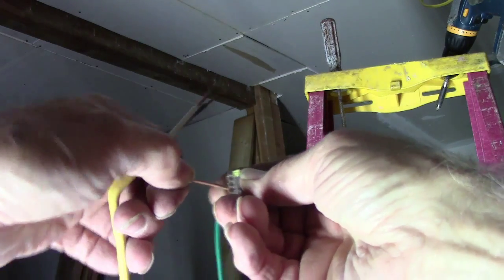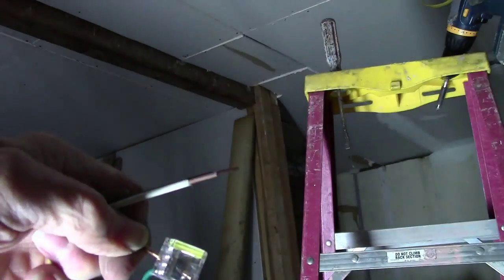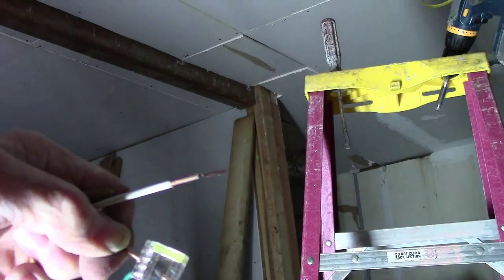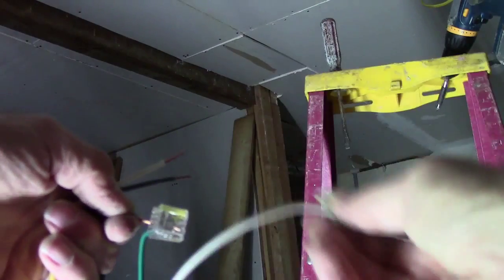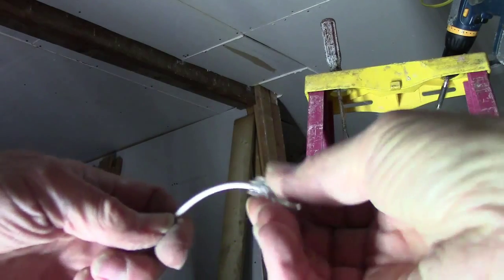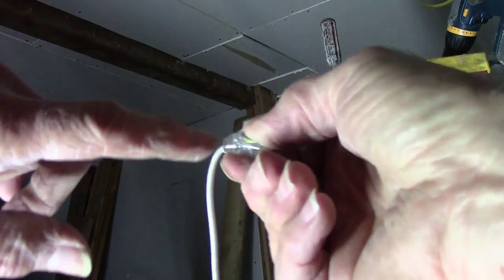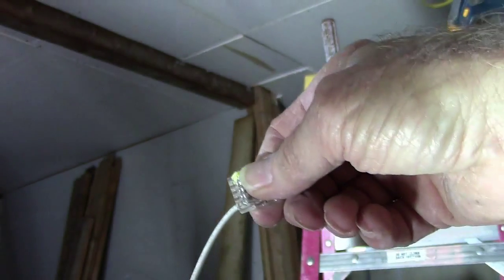Just twist it and push it in. You want to cut them back about three quarters of an inch. When you stick them in there, you just want to make sure there's no bare wire coming out of your plastic wire nuts.